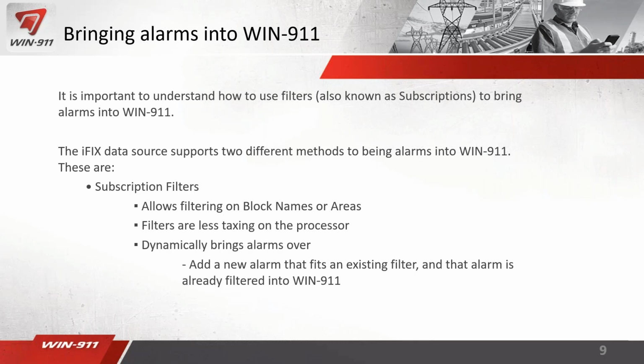This allows filtering on block names or areas. They're much less taxing on the CPU and overall performance. And it's also just really good for future proofing because it dynamically brings alarms over. So if you add a new alarm that fits the same exact existing filter criteria, the alarm is automatically going to be filtered and caught by that filter and sent to the correct strategy, as opposed to manually adding an alarm every time you add one over on the iFIX side.